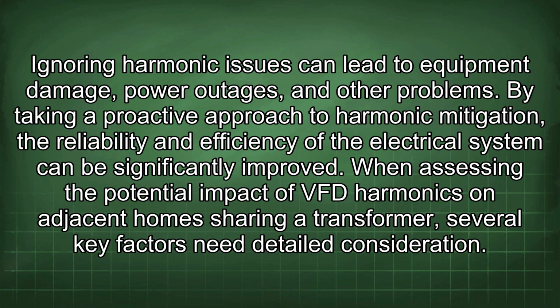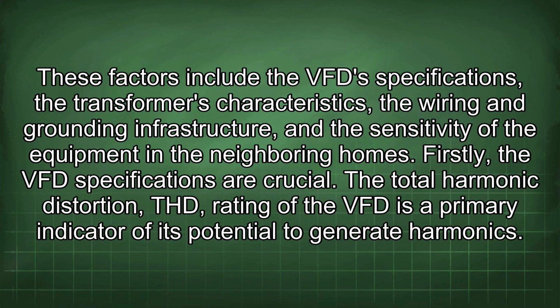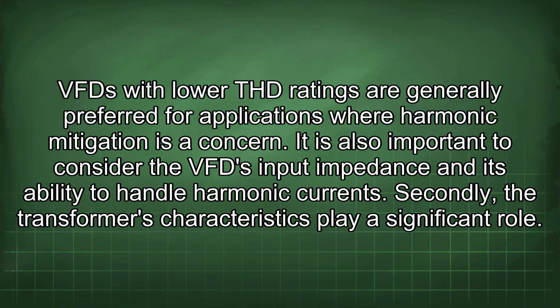When assessing the potential impact of VFD harmonics on adjacent homes sharing a transformer, several key factors need detailed consideration. These factors include the VFD specifications, the transformer's characteristics, the wiring and grounding infrastructure, and the sensitivity of the equipment in the neighboring homes. Firstly, the VFD specifications are crucial. The total harmonic distortion (THD) rating of the VFD is a primary indicator of its potential to generate harmonics. VFDs with lower THD ratings are generally preferred for applications where harmonic mitigation is a concern. It is also important to consider the VFD input impedance and its ability to handle harmonic currents.